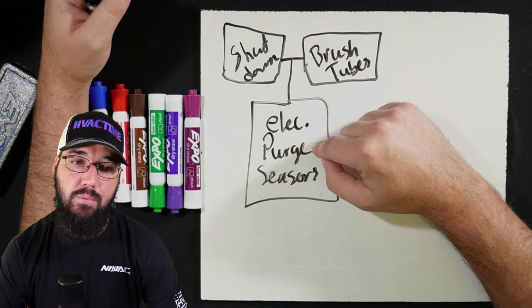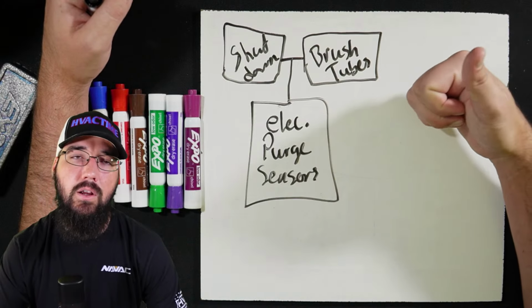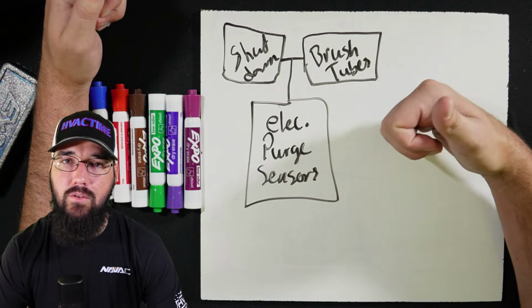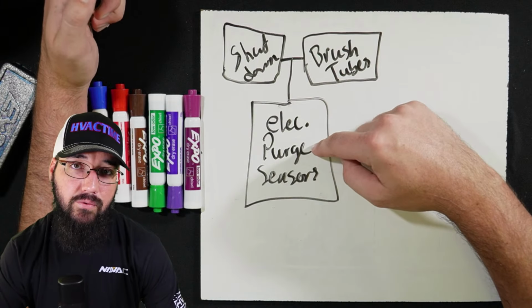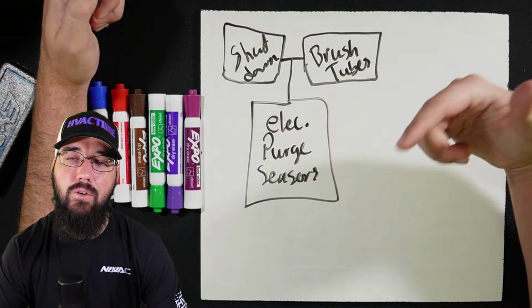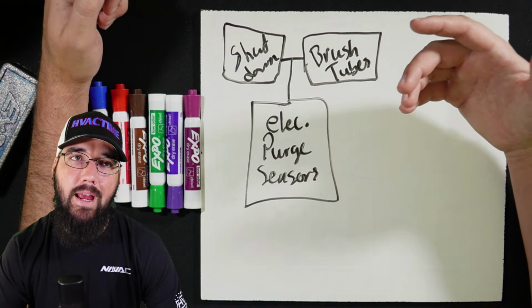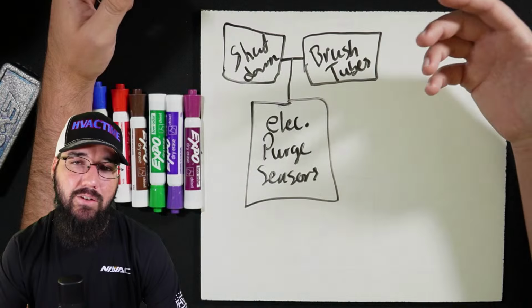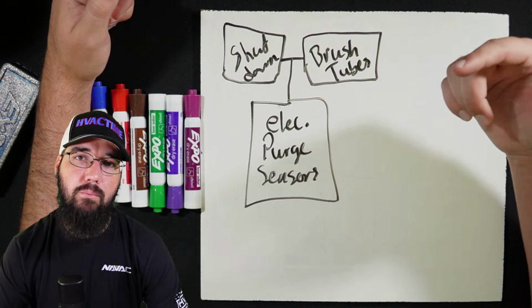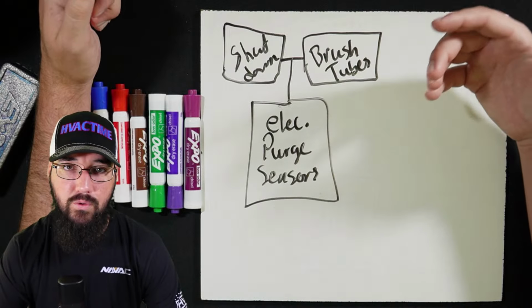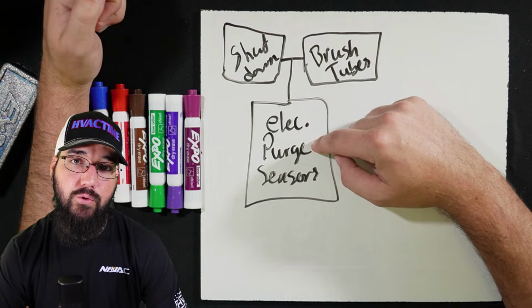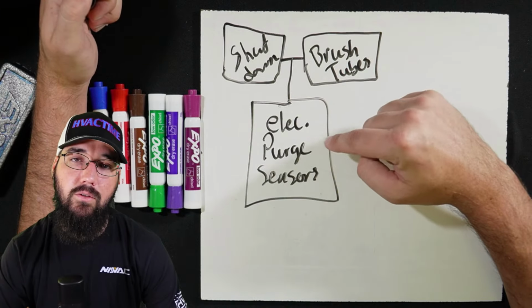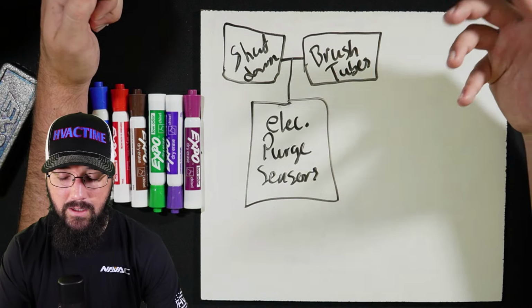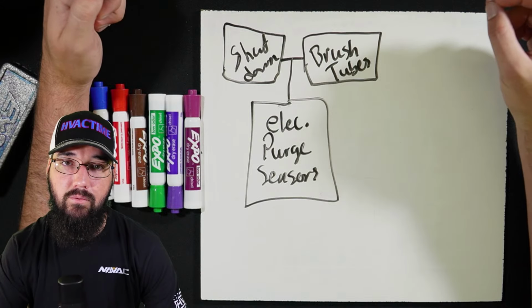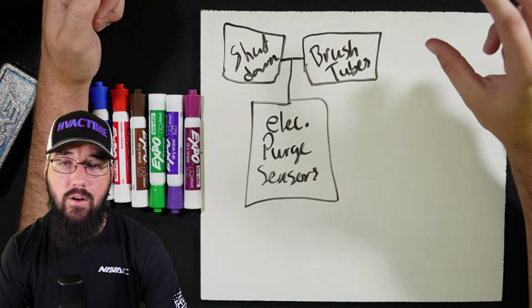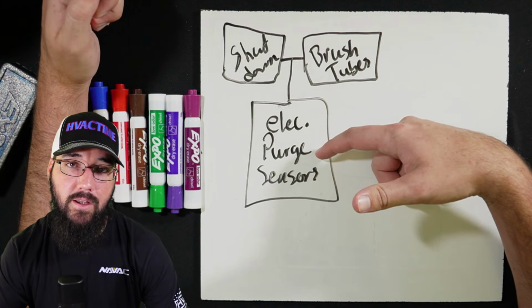Yeah, electrical, and then purge. By purge, I'm talking we're going to service the filter. In some cases, the customer may want to change out the purge valves, so the pump out valves specifically, during an annual. Whether you do it annually or on a 3 to 5 year cycle, it is recommended to do that because those pump out valves go bad so frequently on those machines. They cause a lot of nuisance non-condensable issues. I know Trane, local to me, that is their standard procedure. They go in to do maintenance on these as part of their annuals, at least that's my understanding. They're going to change those solenoid valves out entirely, not the coil, but the actual valve. So that may be something that this person can be working on in that process.